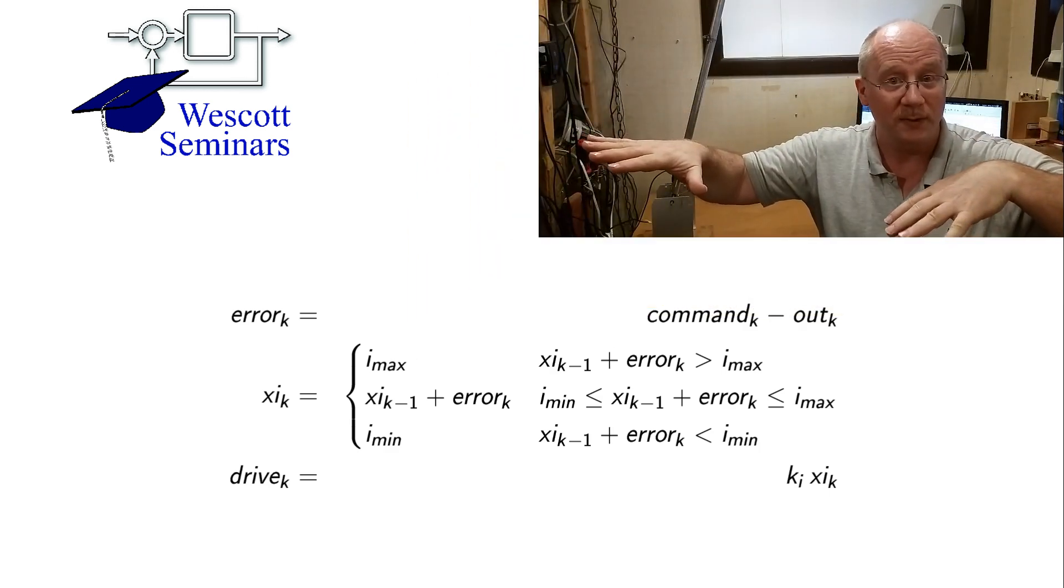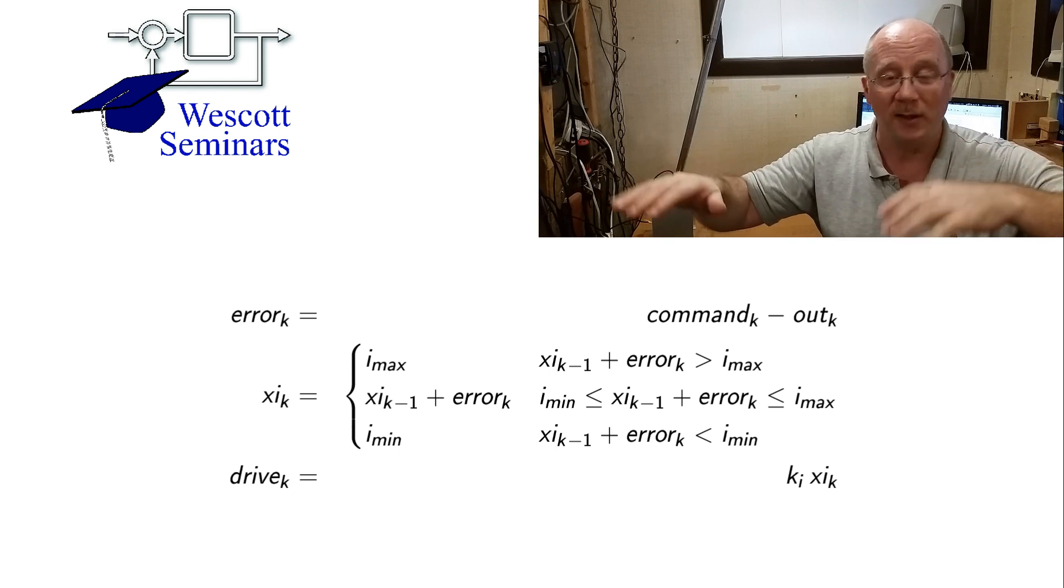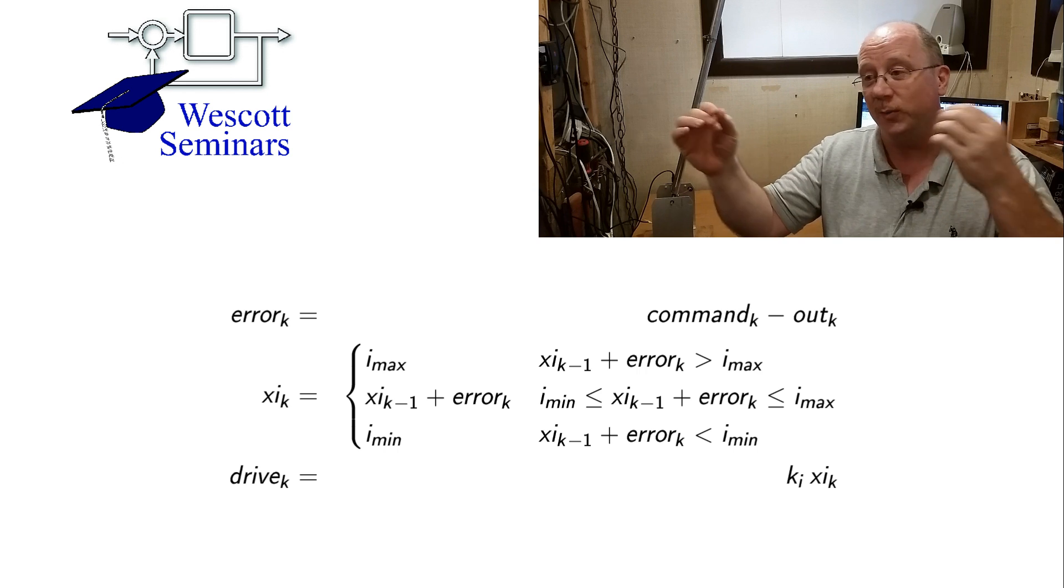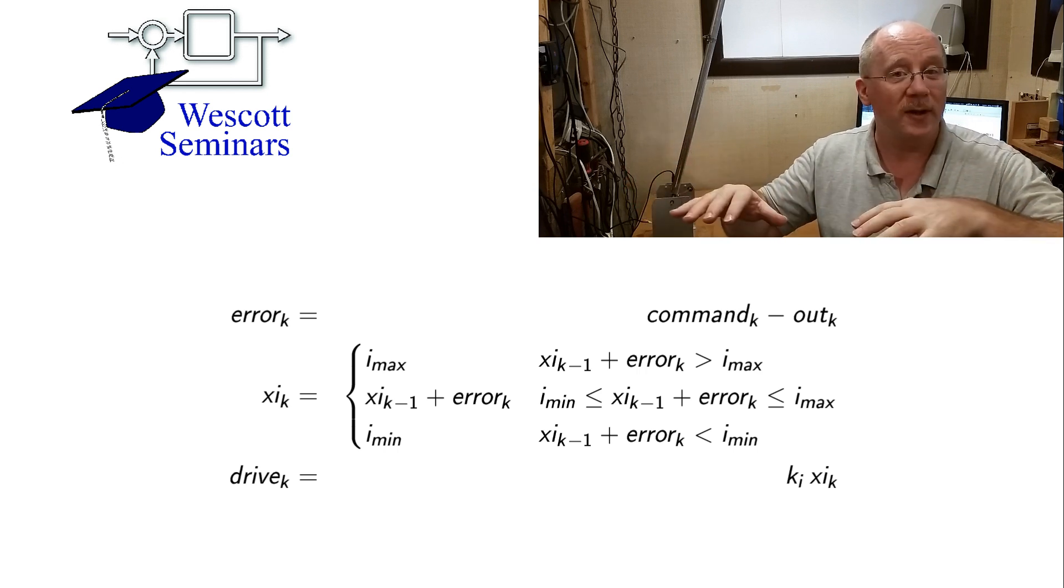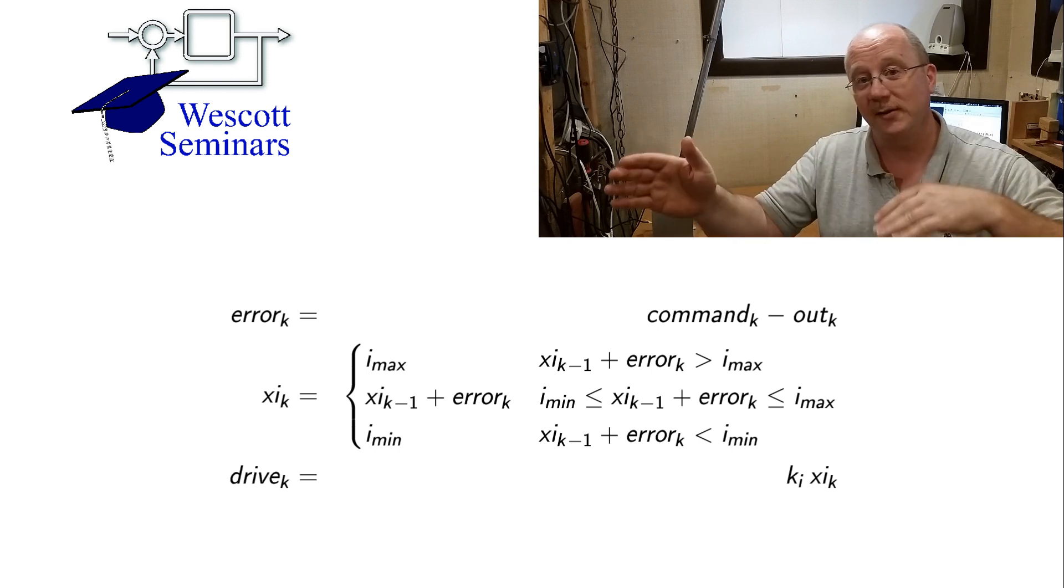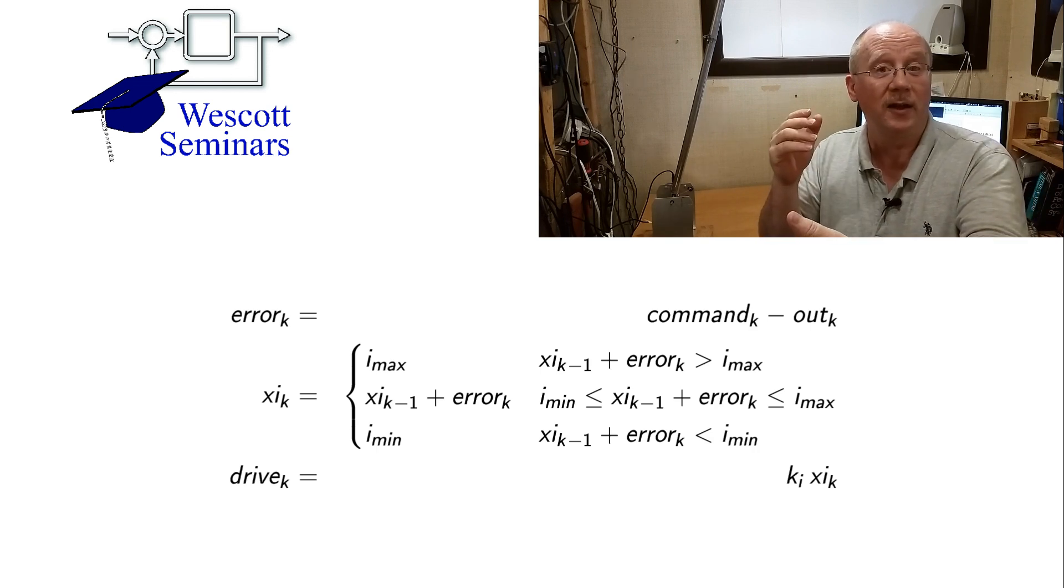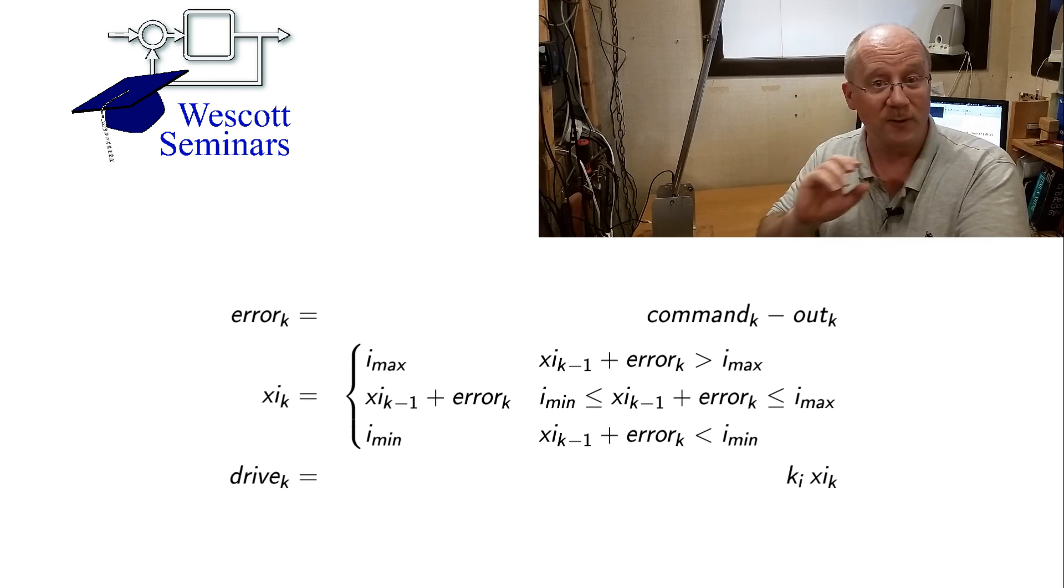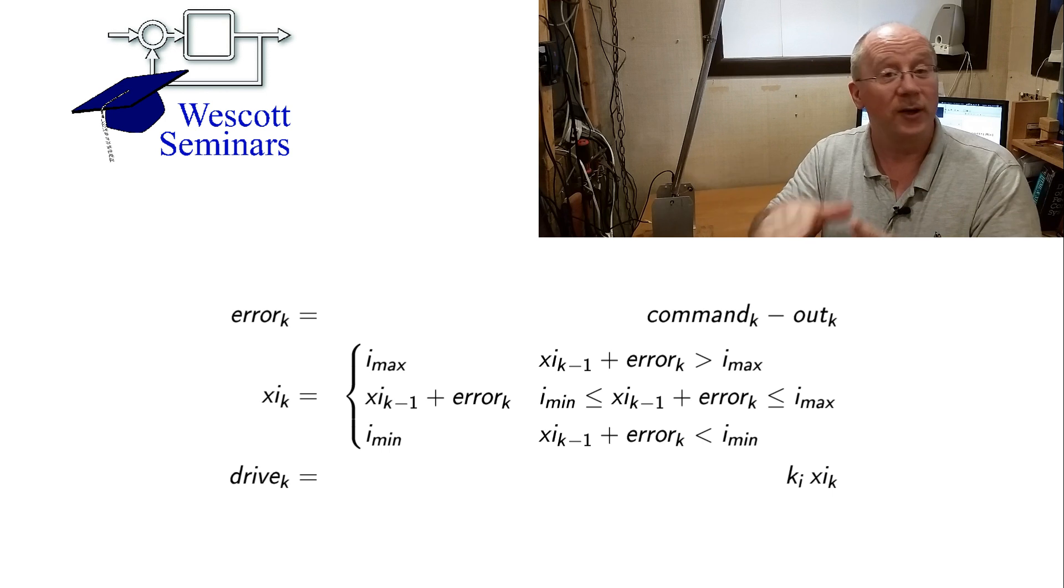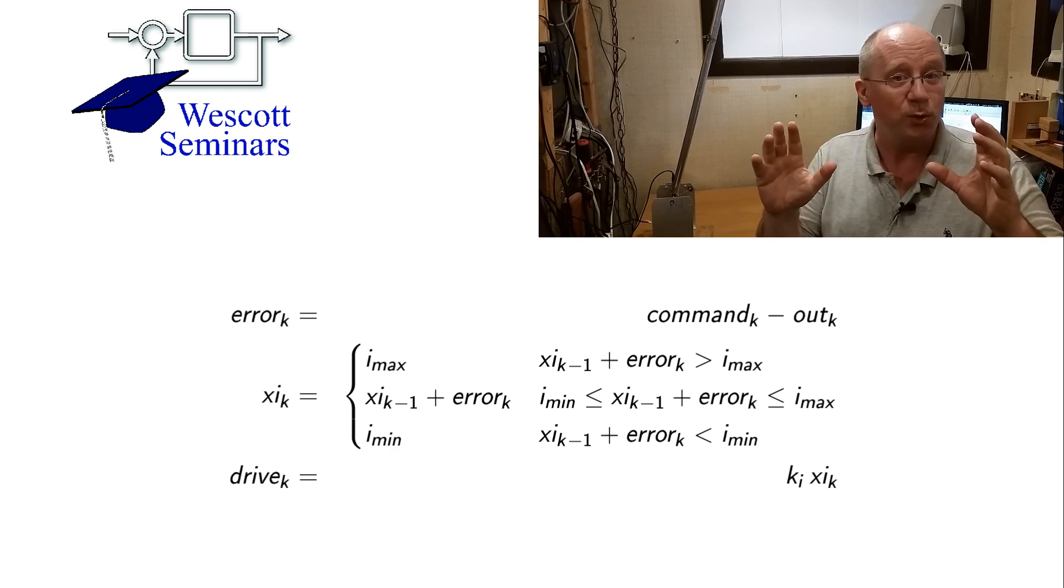Here's the algorithm for computing integrator control when you're using integrator anti-windup. Now this looks a lot more complicated, but basically, it's only the part in the middle that looks bad. So you're computing the error as usual, and then what that part in the middle says that as long as your integrator is not bumping into one of its limits, then just make it a normal integrator. So the way you implement an integrator is that you take the past value of the integrator and you increment it by your error. And then if that thing exceeds a limit, either high or low, then trim it to the limit. And then finally, send it out.